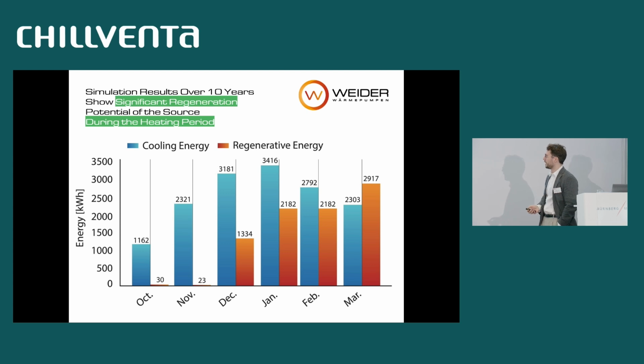and the average regeneration energy per month over the last 10 years in this case. And you see the blue bars are the cooling energy, so actually what the heat pump takes from the source, and the orange bars are the regenerative energy from the geoAir, so the energy which will be restored during the heating period. You can see the orange bars are pretty low in October and November. That's because the source temperature is still very high after summer, 10 to 15 degrees. And so the delta T compared to the outside air and the exhaust air is not very large. So basically there's no regeneration during this period. But when the source gets cold, starting in December, you can see the cooling energy rises, but so does the regenerative energy. And even in March, in this case, we restore more energy than we actually take out of it.